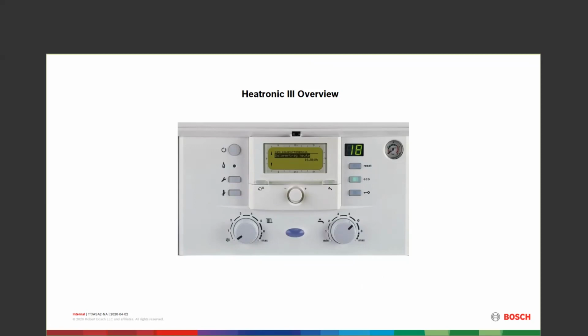From there, our eco or comfort button on a combi boiler. The eco button, when not lit, allows the boiler to maintain temperature on the plate heat exchanger so that if the customer turns the hot water on in a faucet, everything's warmed up. It's all ready to go. We simply go into a pre-prepare of the boiler and we're off and running. If we are set in the eco with the eco button lit up, that green light lit on the eco button, then it can go to room temperature and we do not maintain our plate heat exchanger in a combi boiler.